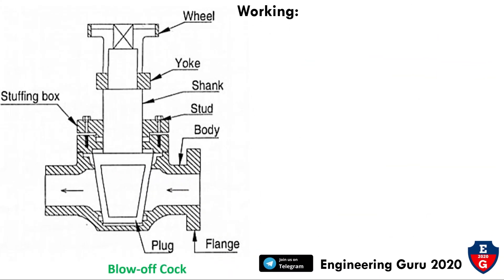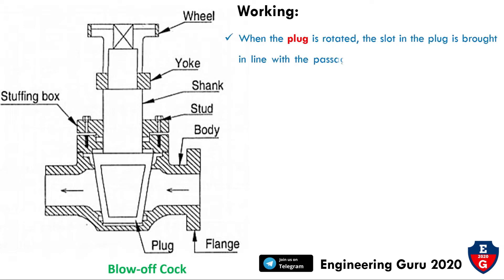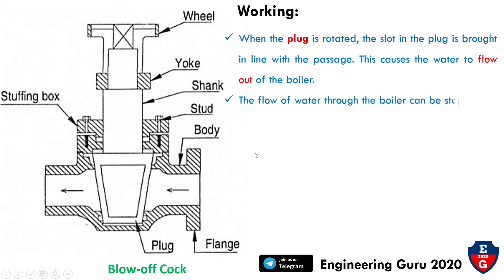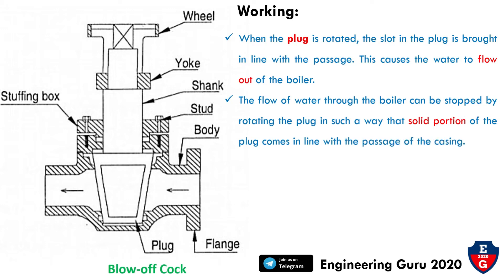Now we will see the working of this cock. When the plug is rotated, the slot in the plug is brought in line with the passage. This causes water to flow out of the boiler. The flow of water from the boiler can be stopped by rotating the plug so that the solid portion of the plug comes in line with the passage of the casing.